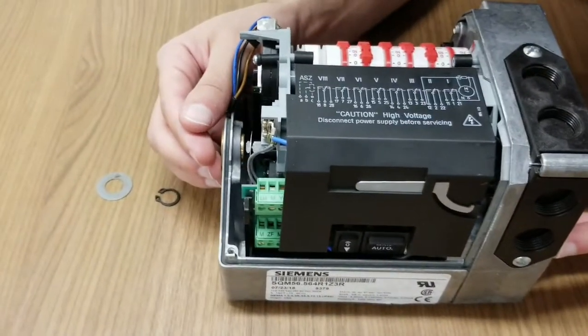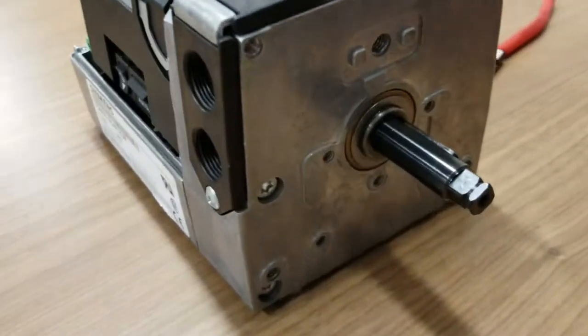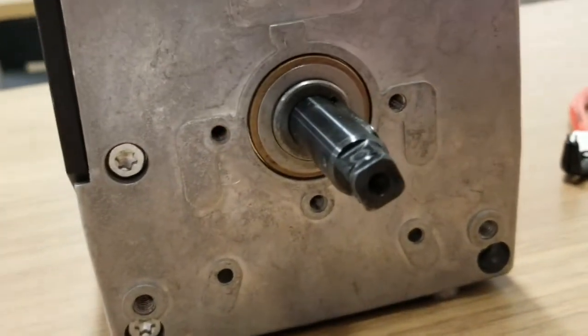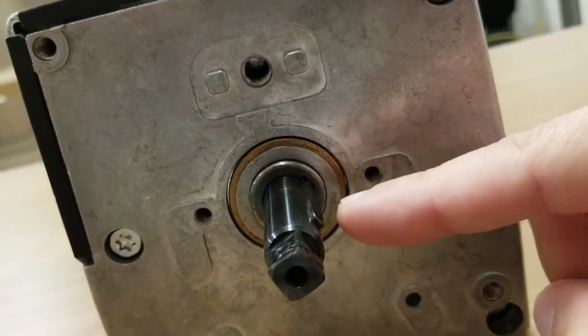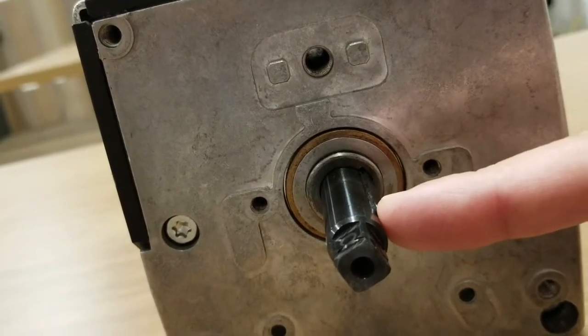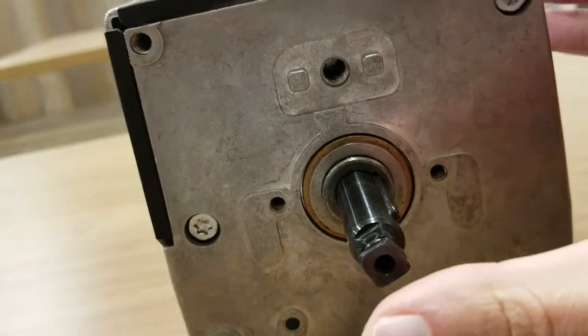Once the washer is on the shaft, we're going to push in the shaft the rest of the way on the actuator. One thing to keep in mind, though, is this key needs to line up with this keyhole. So the key on the shaft needs to line up with the keyhole on the actuator, like so. And I just push it in the rest of the way.